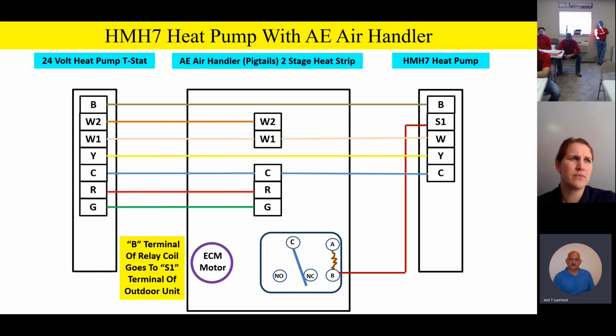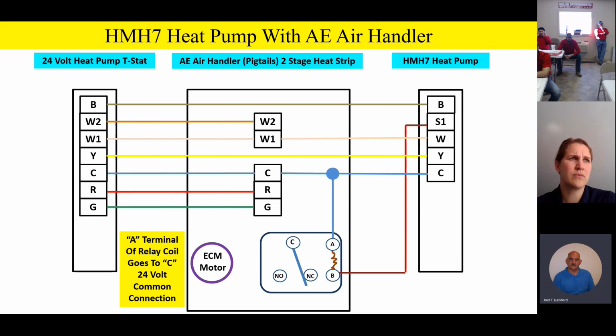Now S1, which we'll talk about in a little bit more, is an output from the outdoor unit to switch that relay when it wants reduced airflow. The other side of the relay coil is going to go up to the common terminal, or you're going to tie it onto the common wire. And what that's going to do is complete the circuit for the relay coil itself. So basically, anytime we have an S1 demand, it's a 24 volt output from the outdoor unit. Anytime we have an S1 output, it's going to energize that relay and switch that coil. Energize the coil and switch the relay is what it'll be doing.